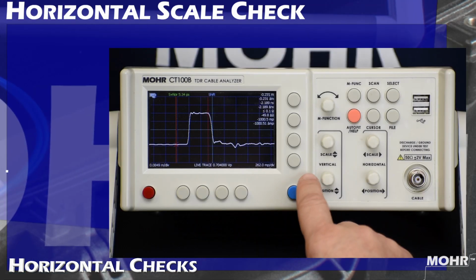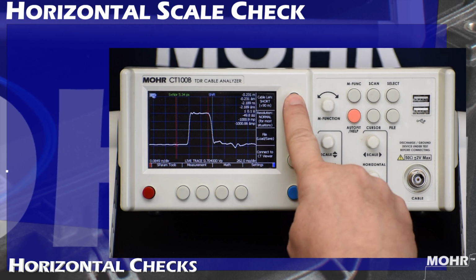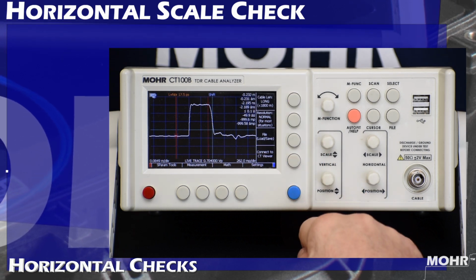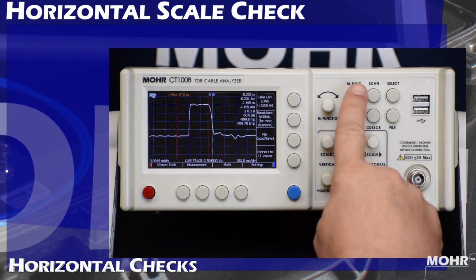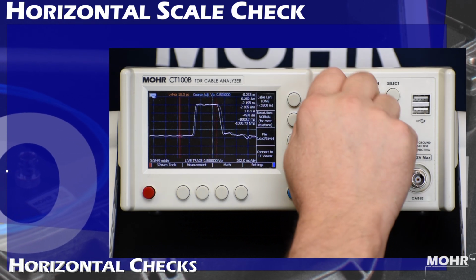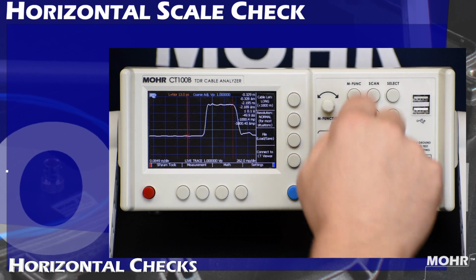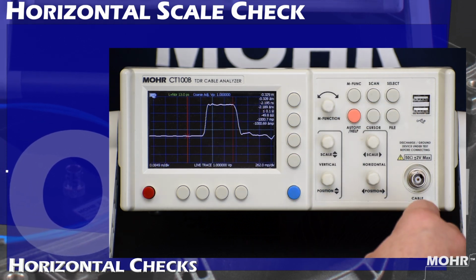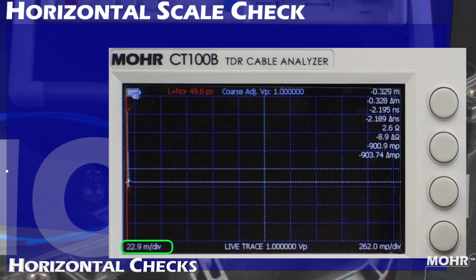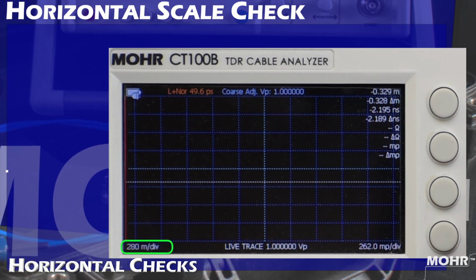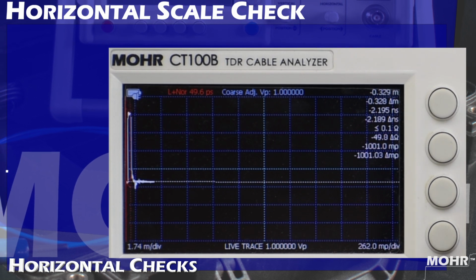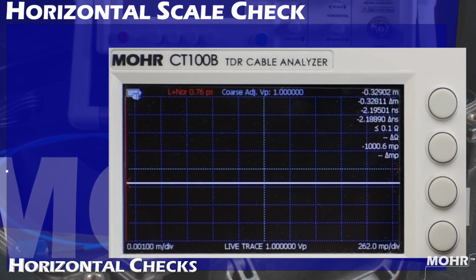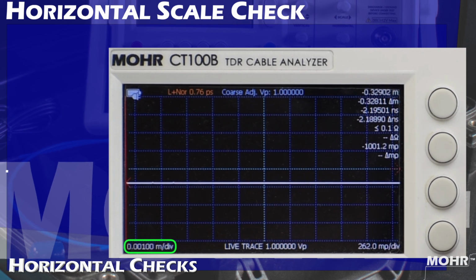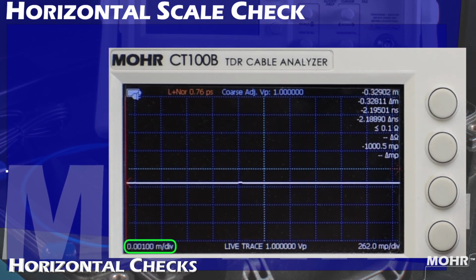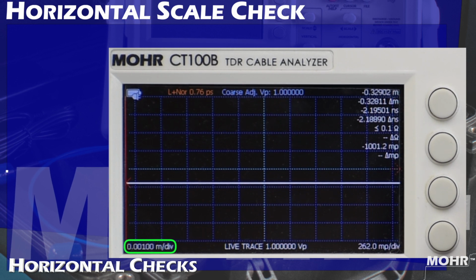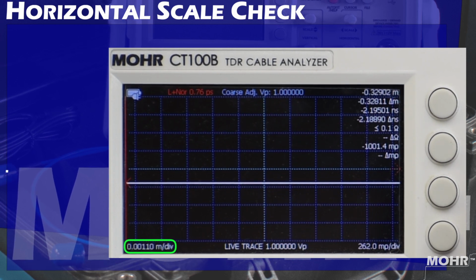For the horizontal scale check, from the main menu, set cable length to long. Using the M function and M function knob, set the VP to 1. Turn the horizontal scale knob counterclockwise. The horizontal scale should increase beyond 61 meters per division or 200 feet per division, and the trace should respond accordingly. Now turn the horizontal scale knob clockwise. Horizontal scale should decrease below 0.01 meters per division or 0.03 feet per division, and the trace should respond accordingly.